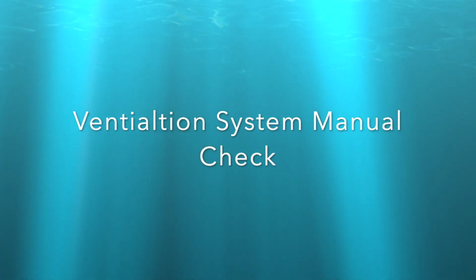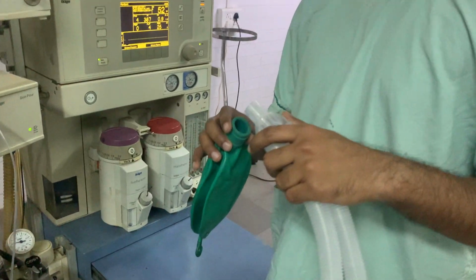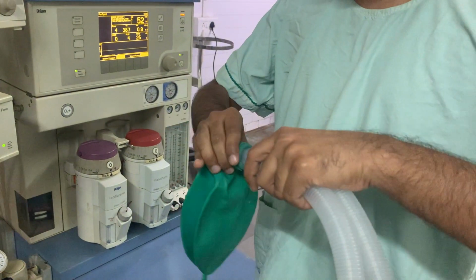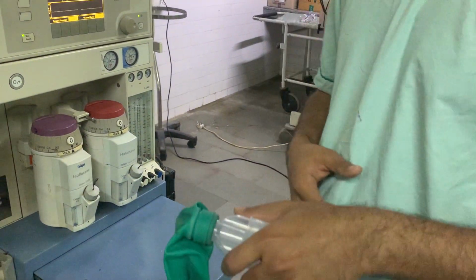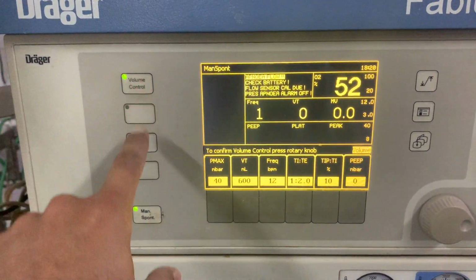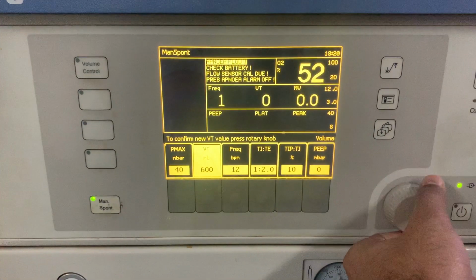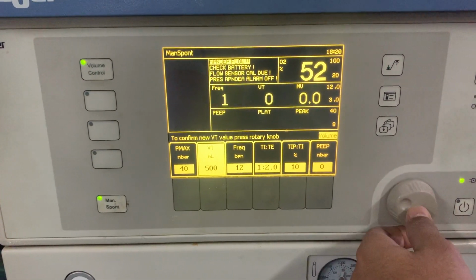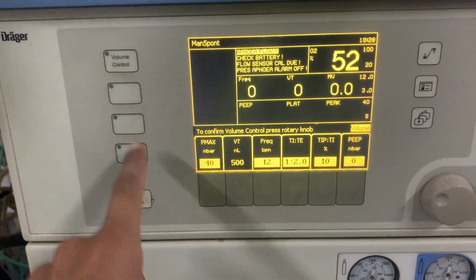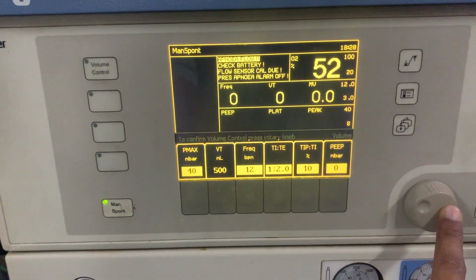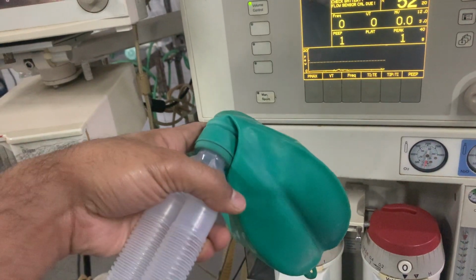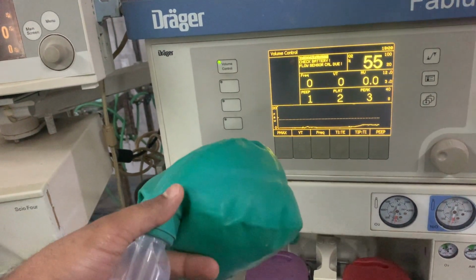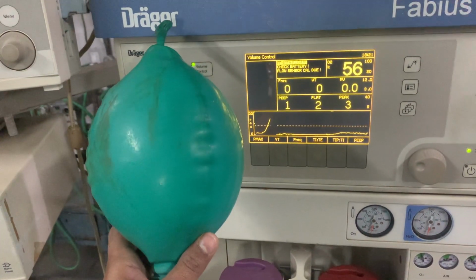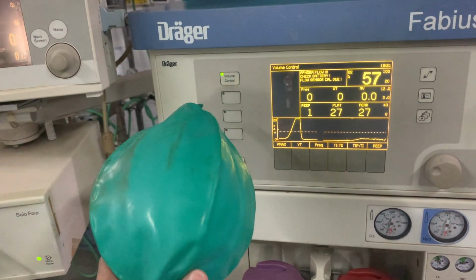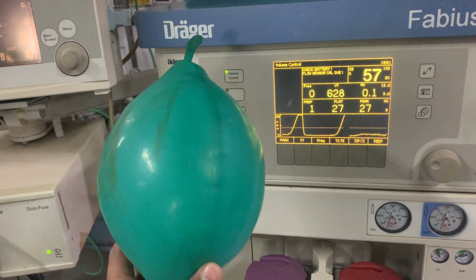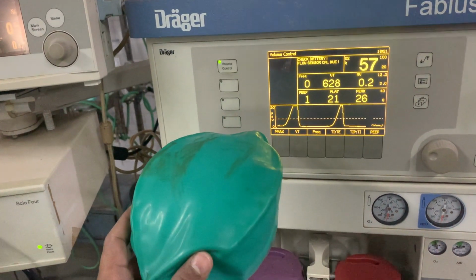Now to check the ventilation system of the machine, place a second breathing bag on the Y piece. Set the machine to the volume control mode or the vent mode. Adjust the ventilator parameters. Set oxygen flow to minimum. Check for proper action of the unidirectional valves. Verify the bellows deliver the correct tidal volume during inspiration and the bellows fill completely during expiration.